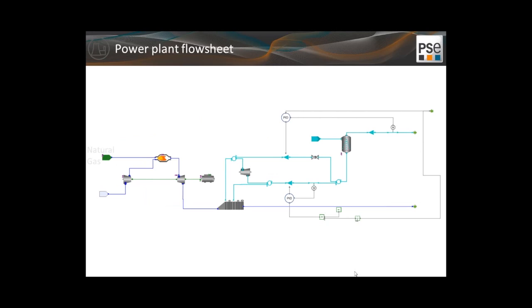Now, 2 potential steam connections to the capture unit reboiler are modeled. In normal operation, Peterhead will use steam taken from the IP-LP crossover for solvent regeneration, with a small amount of condensate spray used to control the temperature in the desuperheater.